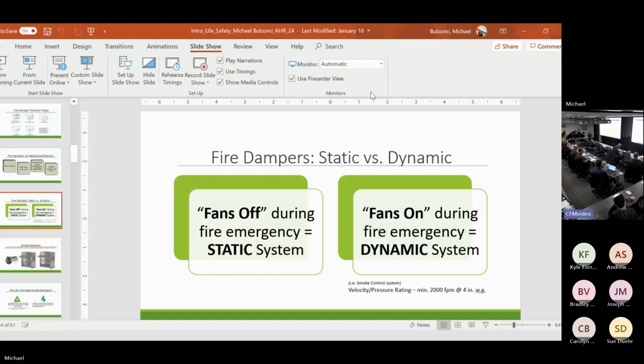So I might have a single section maximum panel allowance static of 36 by 36. Dynamically, I've added 2,000 feet per minute, 4 inches static to close. It's a lot harder. Now my single panel maximum is 24 by 24. Well, if I do an oversized damper, static, I might have been able to do it in 2 panels. Dynamic, maybe I have to do it in 4. My cost just went up exponentially. So you're costing the owner potentially extra money he didn't need to spend. Also, if it's a really big damper, I may not have a listing for it. I can only get dynamic dampers up to a certain size.